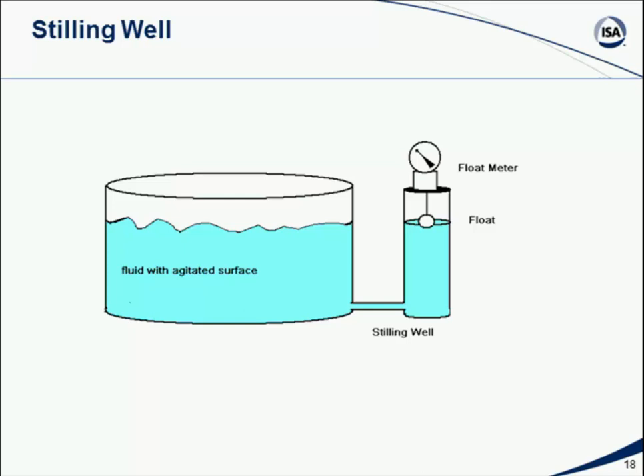Now, one of the problems that you have with a float cable arrangement, of course, is that very few tanks filled with liquids are going to have a float surface that's stable. Whether it's because it's a very large tank and therefore there's just constant wave action as waves bounce around, or because the tank is in operation and therefore I've got liquid pouring into the tank or being drawn from the tank, or maybe I even have to agitate the fluid in the tank and have some kind of mixer. There is the possibility that a float system will be bouncing around because of this and not give me an accurate, stable measurement. So it's also quite often to make use of a stilling well.